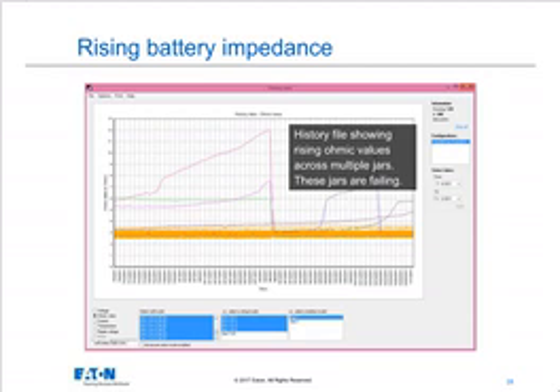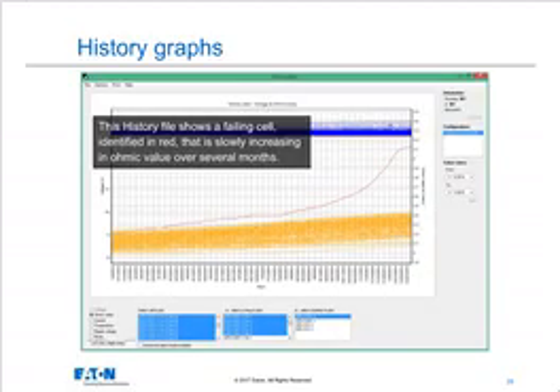And if you were to look at it over a long period of time, you would see that altogether the impedance is rising slowly as the battery ages. But look in the top half of the graph. You see there's several batteries here where the impedance has risen very quickly, and that's a bad sign. That means that cell is actually failing. And then you see the curve drop back down into the orange range. That's when that battery was replaced by the user. So the impedance drops immediately back into the acceptable range. So this kind of thing allows you to track the battery's performance over time.